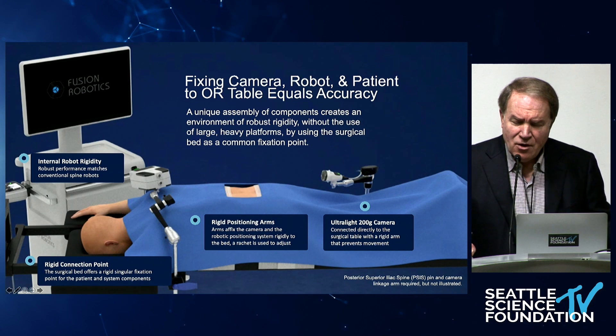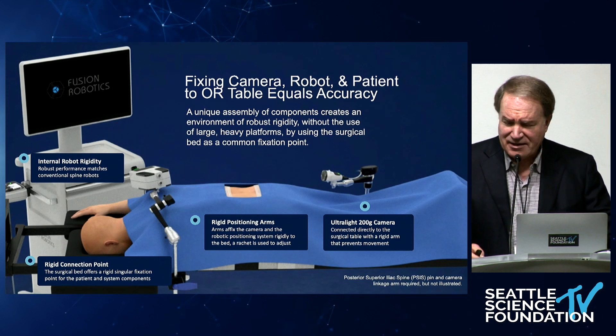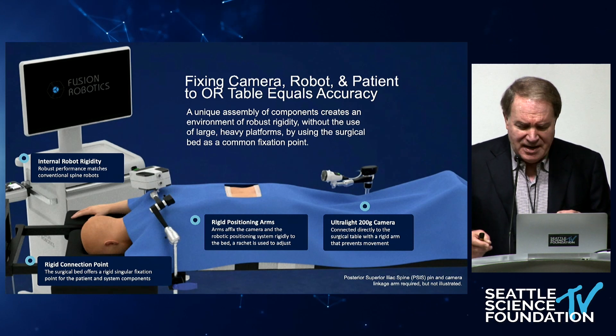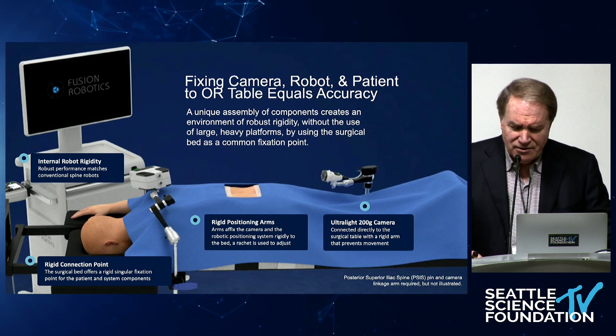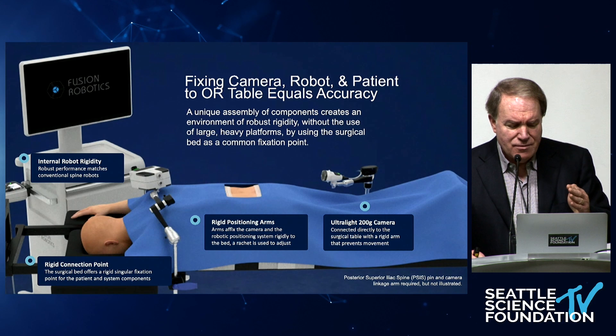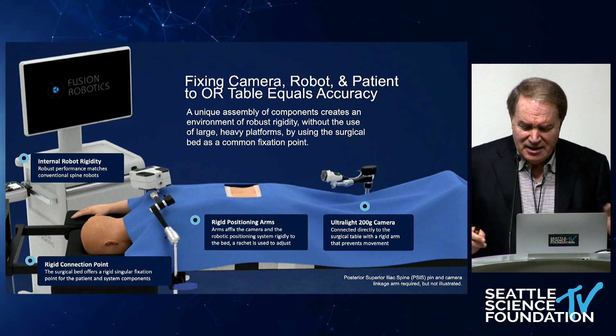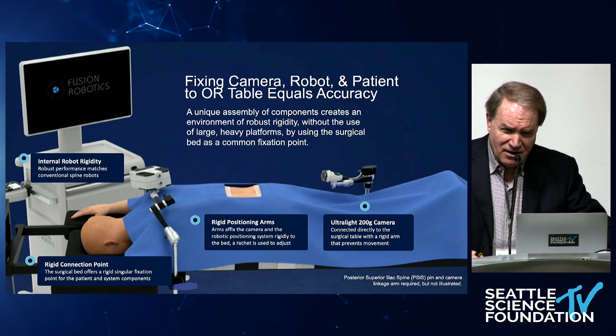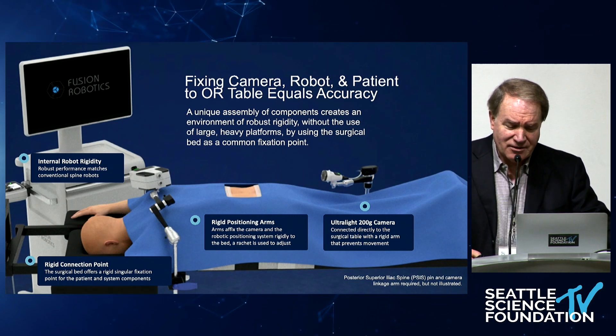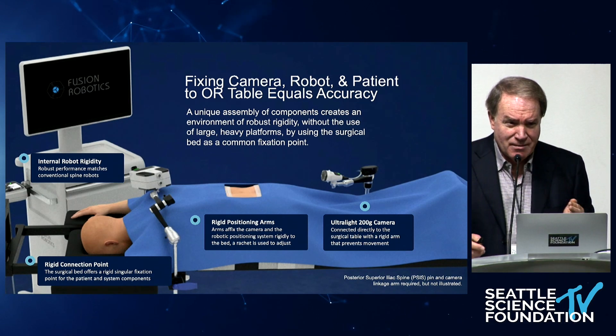It turns out that even though we dynamically reference — and we defined dynamic referencing as stealth back in the late '80s — the mathematics look good on paper. But those little reflective spheres that you use are not quite spherical; there are slight irregularities. So if you move the patient vis-à-vis that camera, or you move the camera vis-à-vis the patient, the incident angle of the light reflected off those spheres changes. In the lab you can watch your image bounce with a standard camera. Move that array for yourselves — you'll see your image go from one place to another.